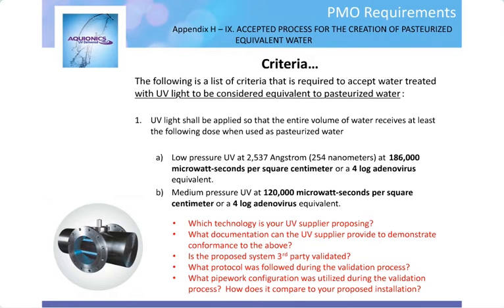So for many of you, I'm sure this probably is not an organism that you test for on a regular basis, but a lot of this information stemmed from the work that the US EPA did many years ago in the municipal drinking water regulation. What they found is that many of the organisms, like the ones we looked at in the previous slide, are highly susceptible to UV at very low doses. But some, particularly adenovirus, have greater resistance to UV than some of these other common microbes that are probably really more of a concern in your organization. And what they found was that the different technologies actually performed a little bit differently on adenovirus.